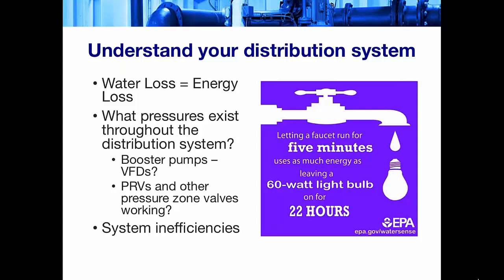You also want to understand the pressures in your system. If you're using booster pumps, are they on VFDs, variable frequency drives? Do you maintain your PRVs, your pressure reducing valves, and any other valves that are used to control pressure zones, whether it's gate valves to isolate? Do they seat properly? Do you have any leakage? All of those lead to system inefficiencies, and system inefficiencies lead to wasted energy. And Nick will talk more about system inefficiencies with our next question.